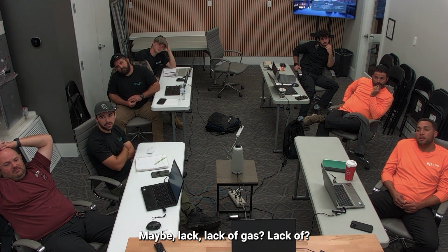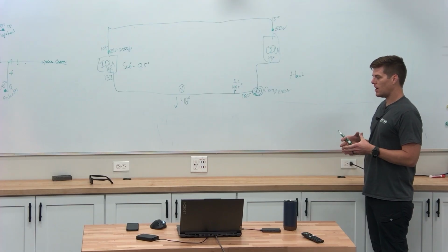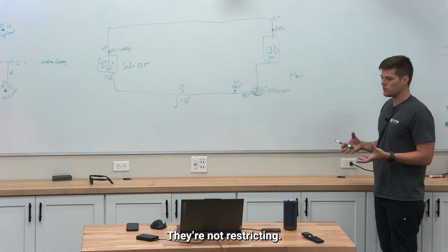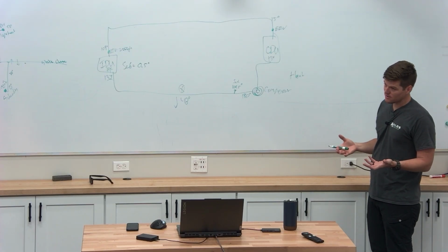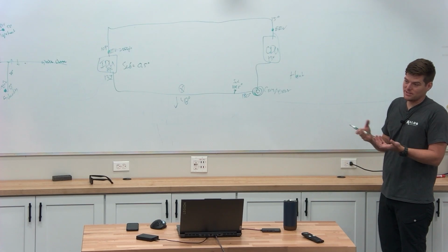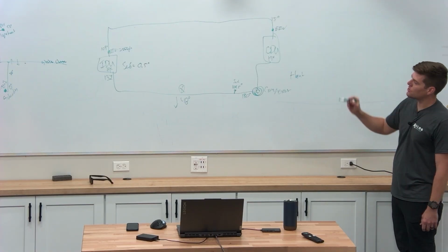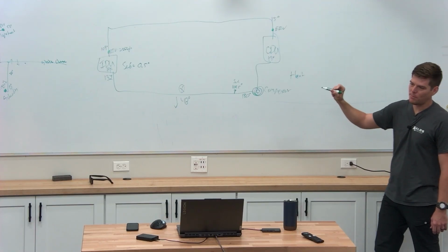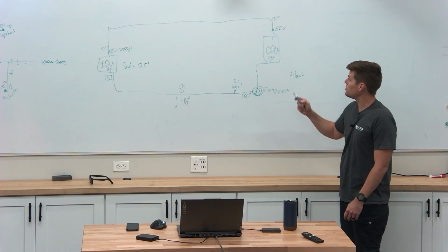Could be a lack of gas, but what do we know the bare bones of expansion valves? They're designed to meter refrigerant. When a valve is wide open, is it metering refrigerant? No. Maybe a little, just because there's stuff in the way. It's colliding with something. But no, the answer is no. We're not metering any refrigerant. It's wide open. It's not getting enough refrigerant. So that's at 2,000 pulses.